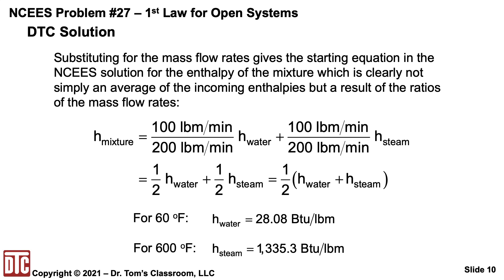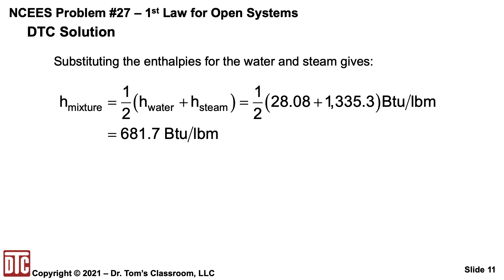From the steam tables in the reference handbook at 60 degrees and atmospheric pressure, h of the water is 28.08 BTUs per pound-mass. Putting those two values in and dividing by two gives h-mixture equal to 681.7 BTUs per pound-mass.